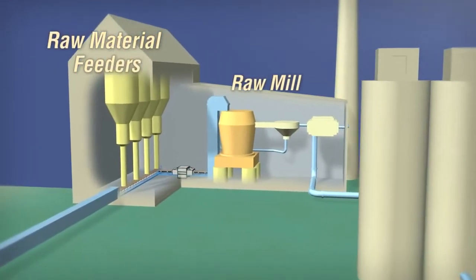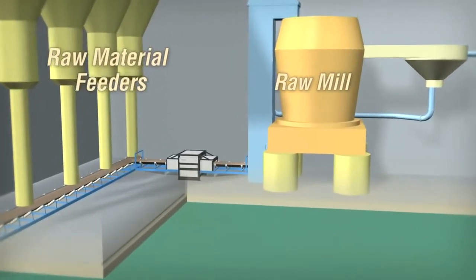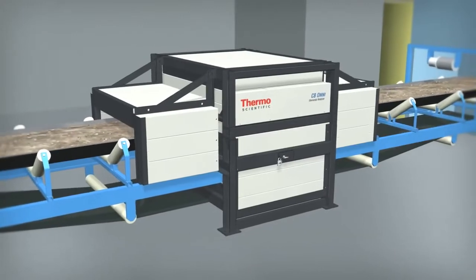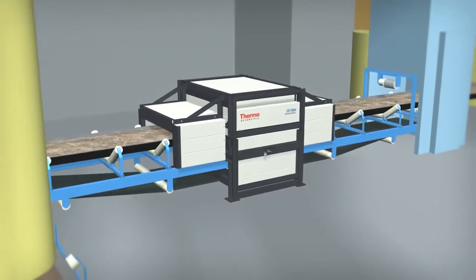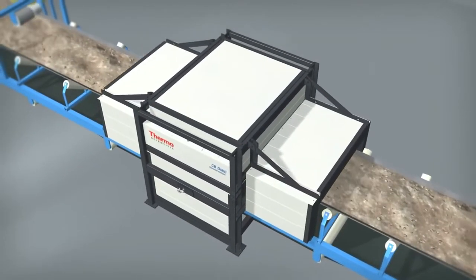In the raw mix proportioning area, the analyzer is located after the raw material feeders but before the raw mill. The system analyzes changes in the raw material additives and responds rapidly by automatically adjusting the raw material feed rates.